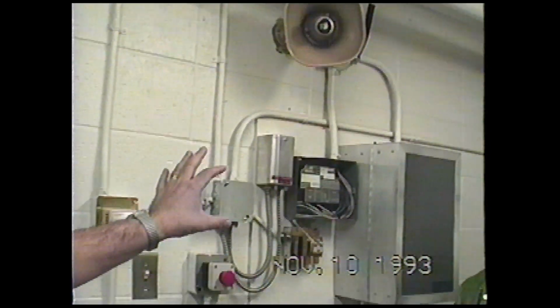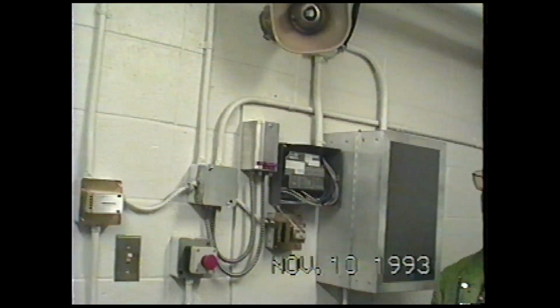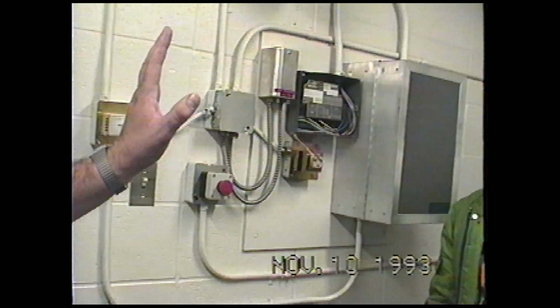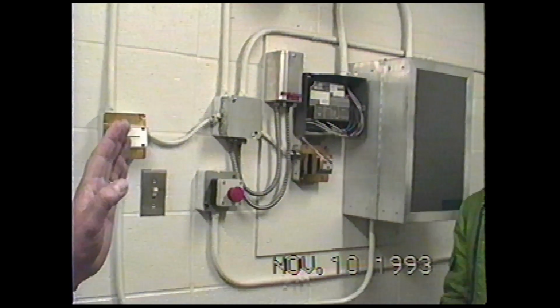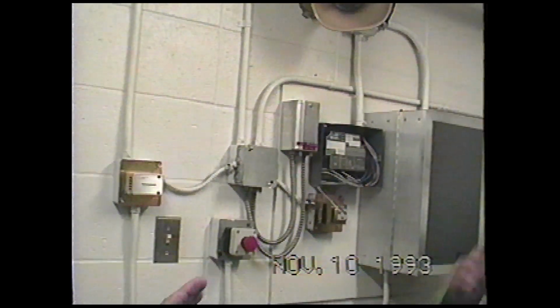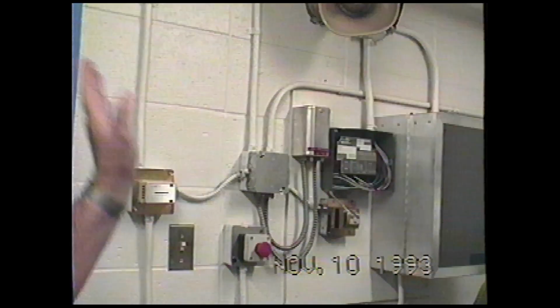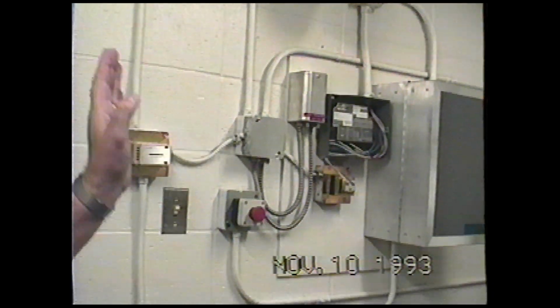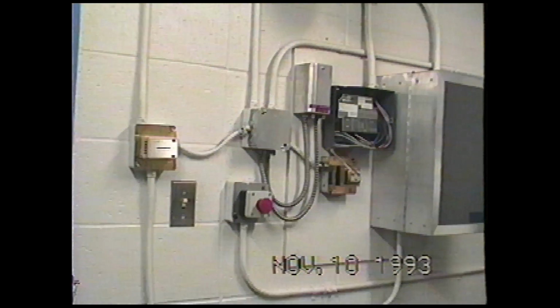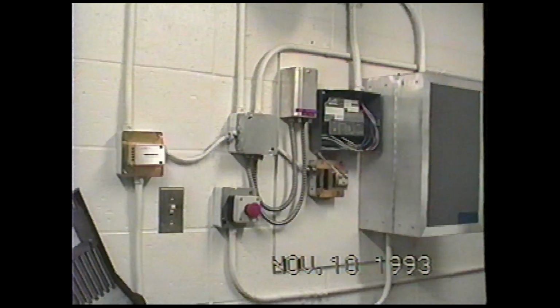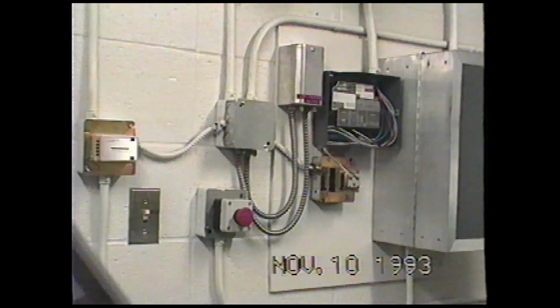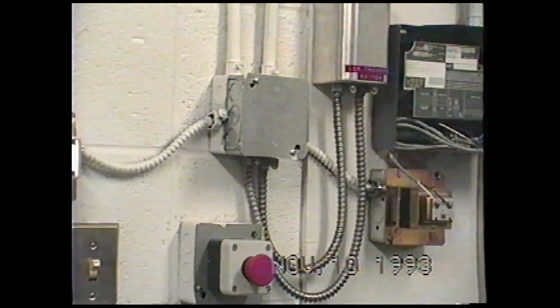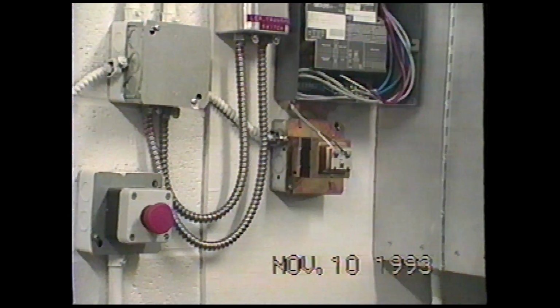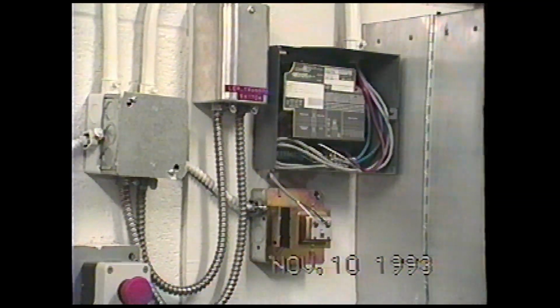The other thing we should point out is this transfer switch. There's a big relay in there that has our Metasys equipment on normal power. If you lose normal power, that relay will drop out and switch Metasys over to emergency power, so it can run on emergency power. But we were having problems when they were doing load shedding - we were losing these things during the transfer. So this is to fix that problem.